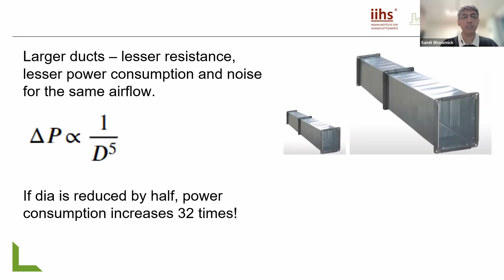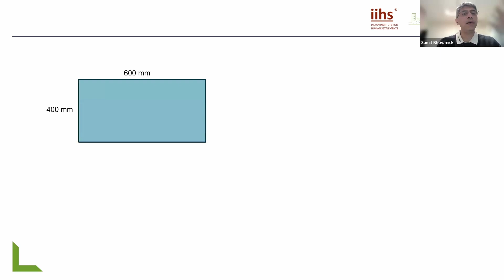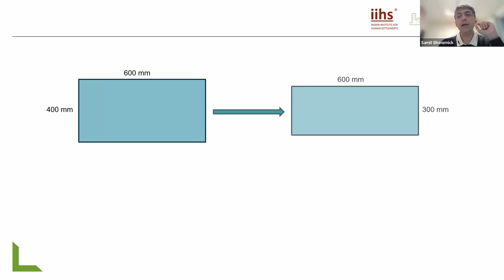I've seen so many projects where a lot of the time we are debating about this. But such is the impact of just size on power consumption that one cannot neglect it. And to put this in more perspective, let's say we have a duct of 600 by 400 millimeters, and I simply reduce the height of the duct for the same flow rate by 100 millimeters. The fan power consumption increases by 2.5 times.